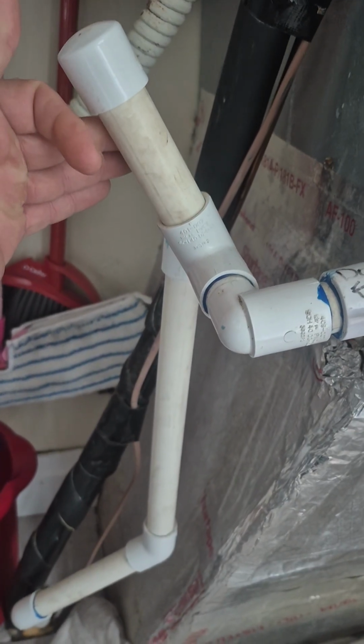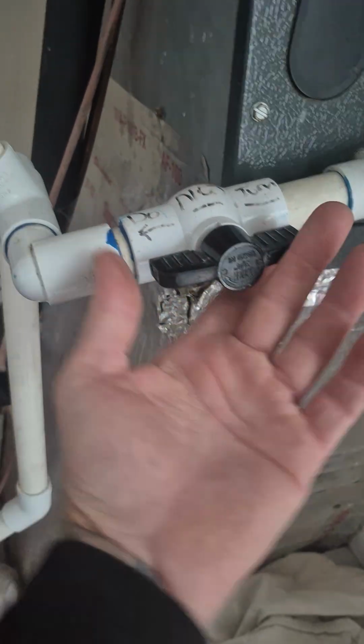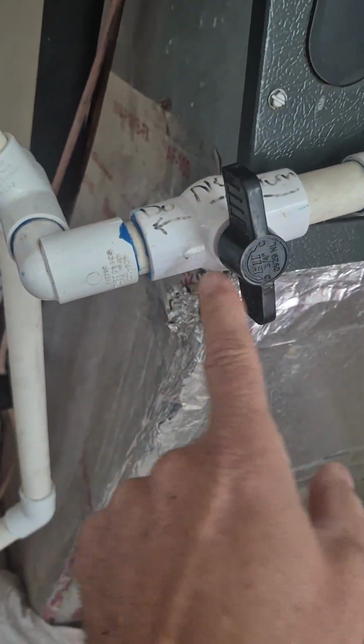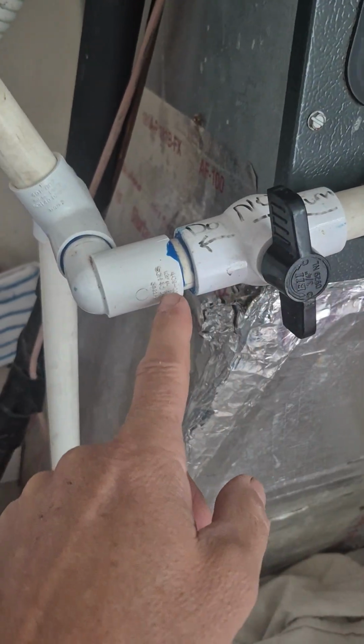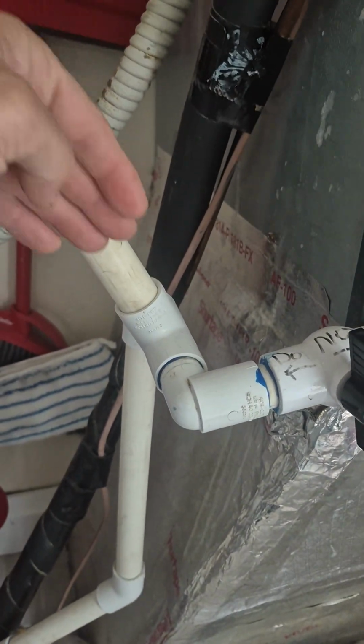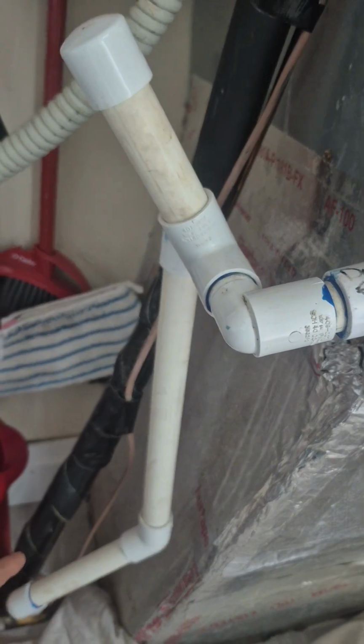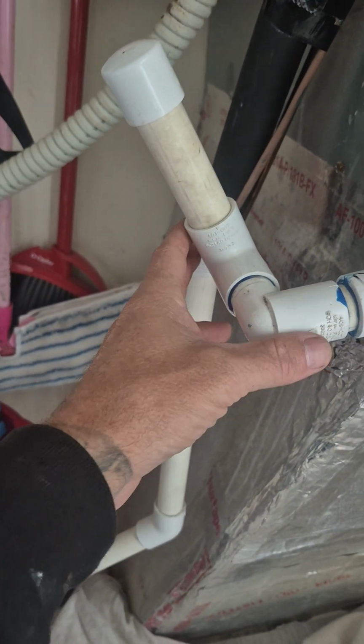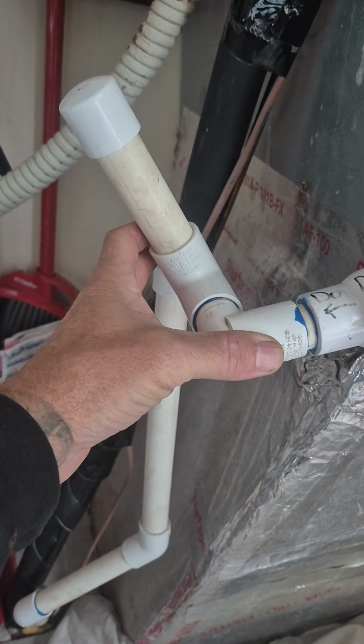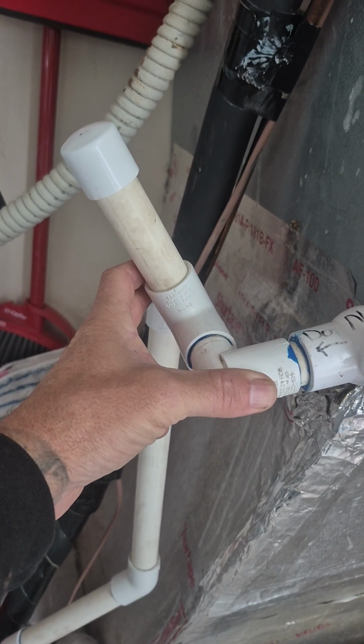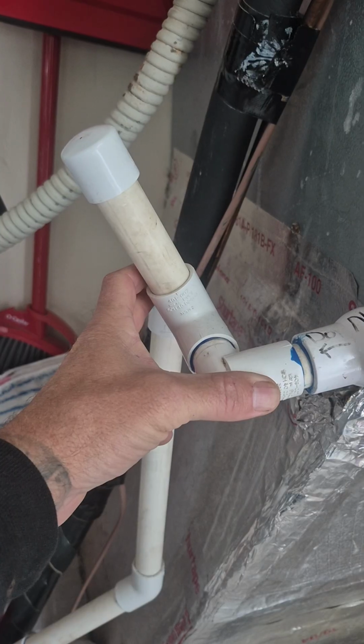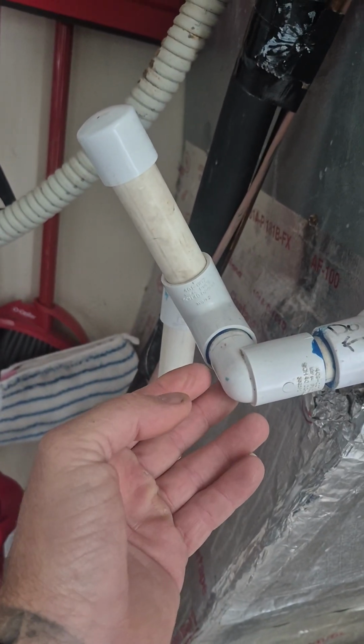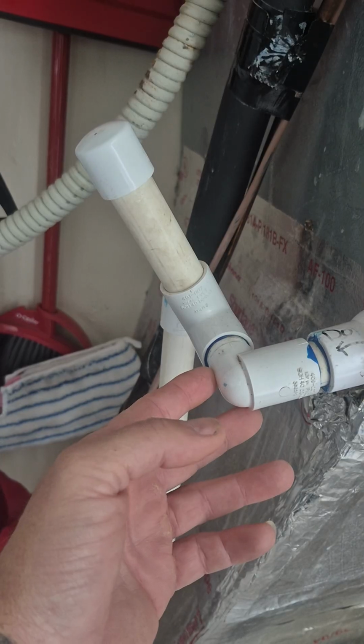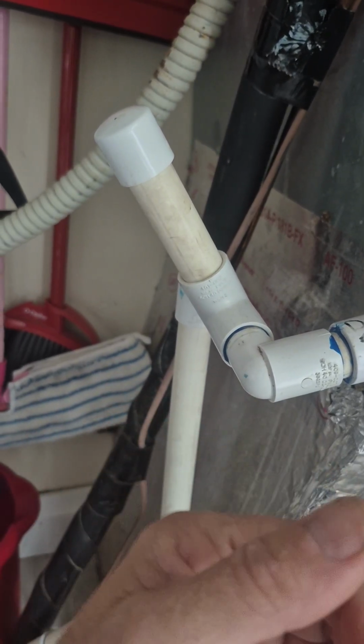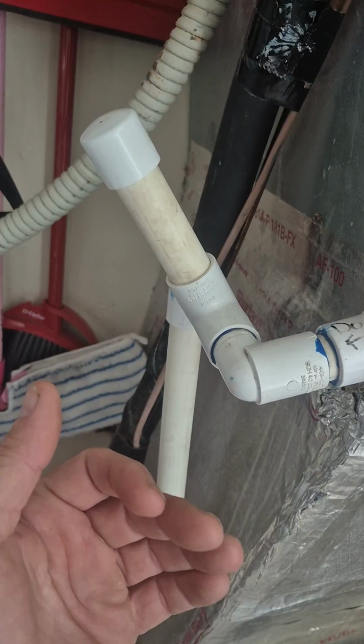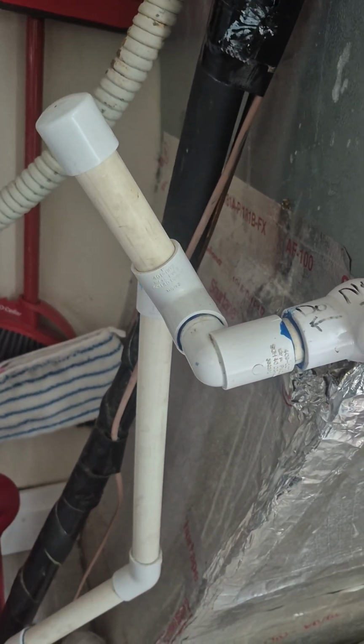That's why this has to be closed, and if you do have a vent, it should be after the trap. This is here so that you can close off the excess water from coming down here and put your hose right here and flush it out with a garden hose, which is much better than using air. You can let it run, and it can really peel off all the contaminants and sludge that's stuck to the wall, whereas air will do it to some degree, but there's not as much friction for it to really pull the contaminants off, and that's just in my experience.